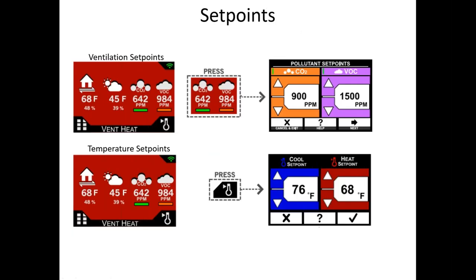The set points then, we'll cover this as something that's changed recently, but the main settings are the CO2 and VOC set points in parts per million. And then you're setting a heating and cooling set point as well. So the CERV is looking at these to decide what mode of operation it should be in, from the previous slide. It's also taking into account the outdoor conditions relative to inside to make optimal decisions based on efficiency. So you're setting these set points, and then the complexity is really behind the scenes in the CERV automatically managing these things.